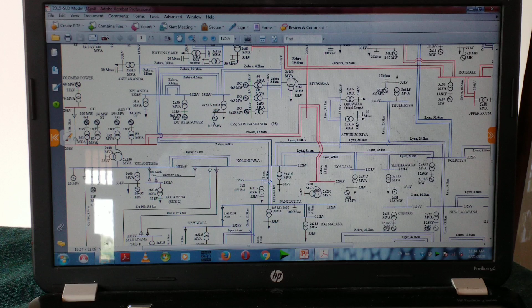Even in the distribution network it happens. Why? In earlier days we were not connecting generators to the 33 kV network, but right now we are. For instance, most of you have solar connections - that is generation connected to the low voltage network. We also have mini hydropowers; in Sabaragamuwa we have almost 200 megawatt capacity of mini hydro, all connected to the 33 kV network.